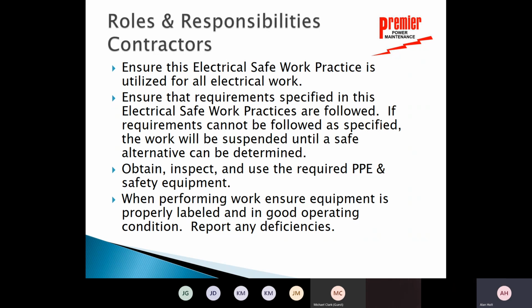Then we have an obligation to make sure that we have the proper PPE and all the proper safety equipment, and we use it properly, and we return it to its proper location. And finally, under their list of roles and responsibilities for contractors, when we work on that plant electrical equipment, we have to make sure it's properly labeled. If you don't see a piece of equipment that's properly labeled, that's a stop work situation. If it's already down, then it doesn't come back energized until it is properly labeled.